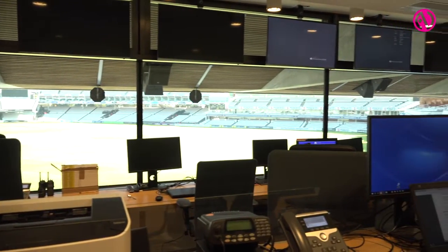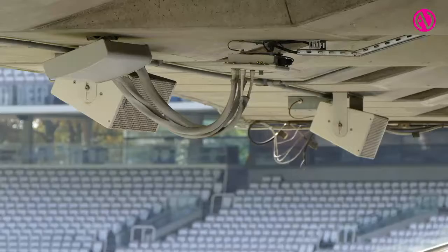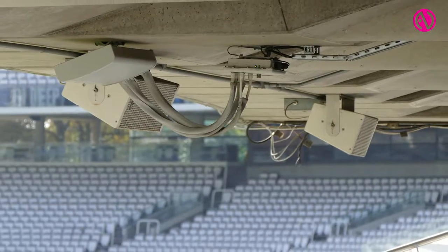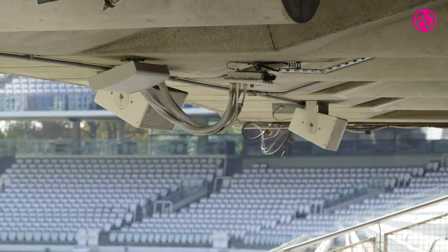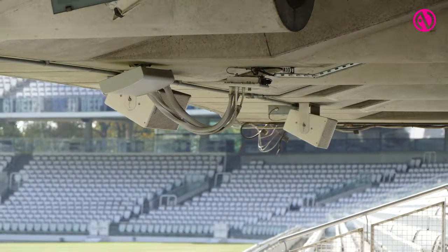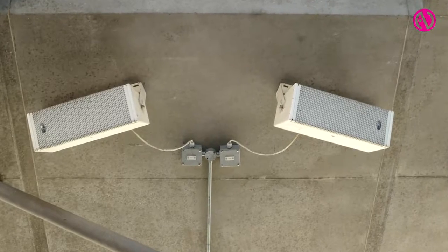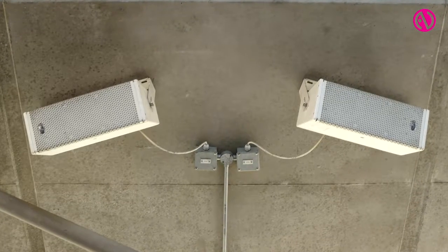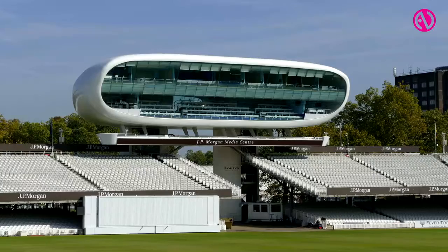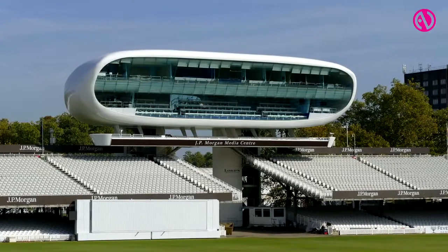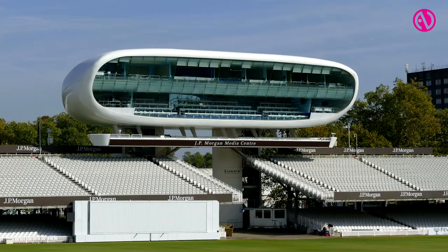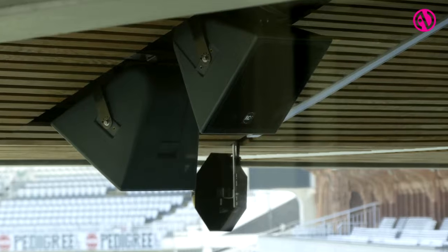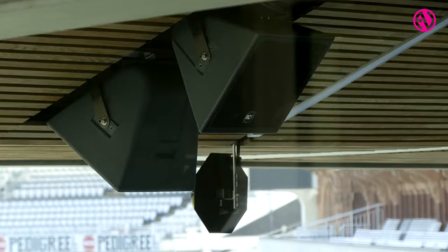And that is also especially useful because this is all voice alarms, so we have what are called A and B circuits, redundant circuits, so in any one area you have two loudspeakers but fed from different amplifiers. So the wiring of that can end up being complicated with all the cross-patching of circuits between adjacent amplifiers. So the fact that we don't have the additional complexity of 100-volt line amplifiers and low impedance amplifiers is very helpful. Just makes it easier to engineer and then afterwards easier to maintain.